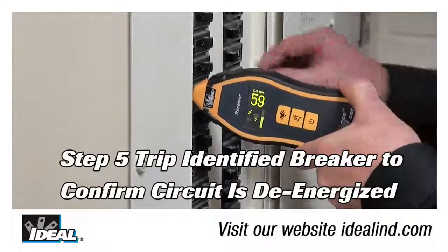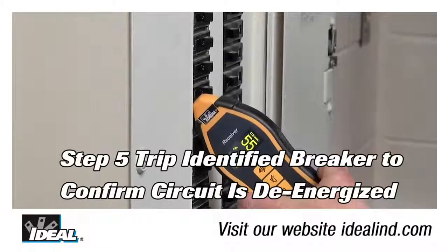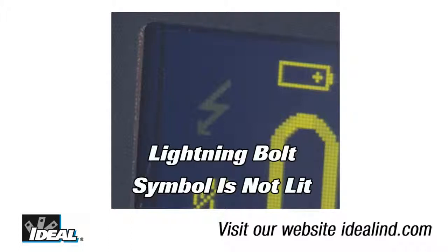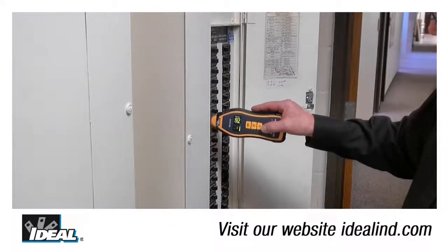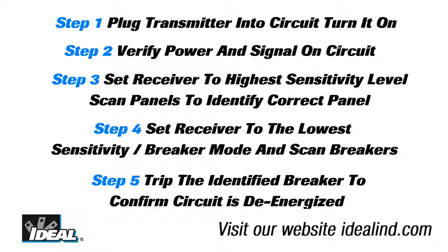Step 5 is to trip the breaker identified by the receiver, and the lightning bolt symbol indicating power will turn off on the receiving unit, indicating the transmitting unit no longer detects power on the circuit. This tells us with a quick look at the tracer that you've tripped the right circuit breaker. Make sure to hold the tip of the receiver on the face of the breaker in the orientation shown for best results. Following these steps when identifying a breaker at an electrical panel will help you find the correct breaker using the circuit tracer.